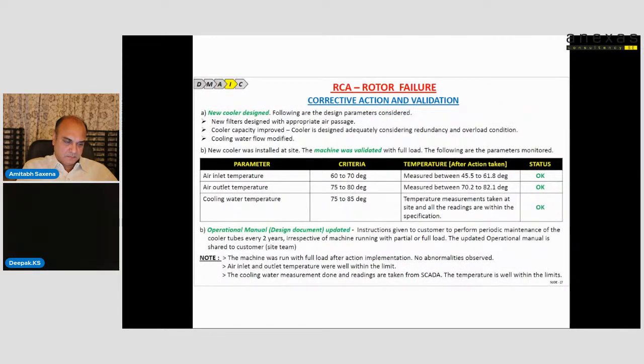Next comes the improve phase where we took the corrective action and validation of the corrective action. The first corrective action is that a new cooler was designed. You can see some of the three parameters we designed. New filters were designed with appropriate air passage, cooler capacity improved, cooling water flow modified. After the corrective action was completed, the new cooler was installed at site. The machine was validated with full load. That was our main concern. At full load, the machine should run without any abnormalities. The parameters were monitored. You can see the air temperature, air inlet, outlet, cooling temperature. It measured within the specification.